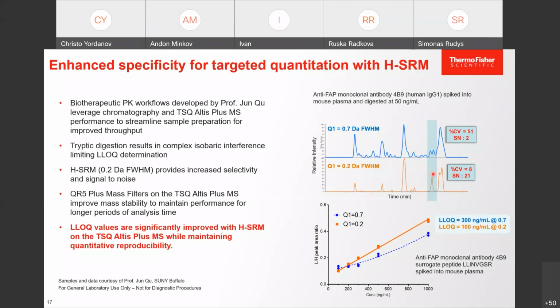And although ion transmission can be lower than with a wider quadrupole window, on the other hand, when we look at signal to noise ratio, on the top chart, we have the quadrupole set at nominal mass, 0.7 Dalton. We have poor signal to noise, because lots of matrix are here. When we squeeze the quadrupole window to 0.2 Dalton, we have filtered out lots of matrix interferences, and we can improve signal to noise around 10 times.